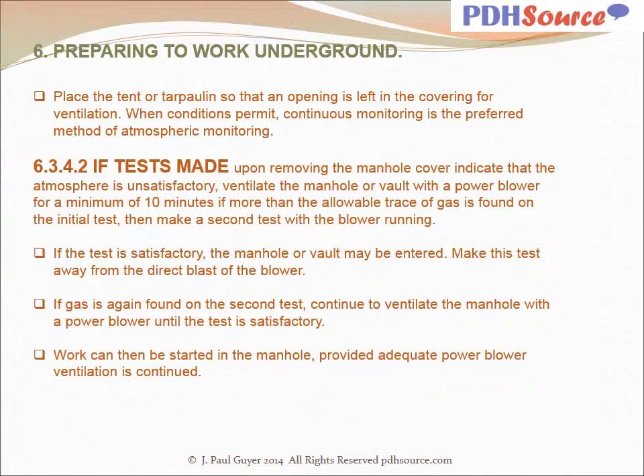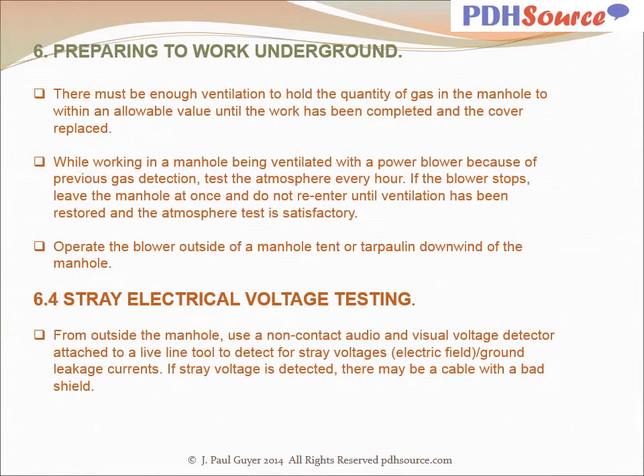Make this test away from the direct blast of the blower. If gas is again found on the second test, continue to ventilate the manhole with a power blower until the test is satisfactory. Work can then be started in the manhole provided adequate power blower ventilation is continued. There must be enough ventilation to hold the quantity of gas in the manhole to within an allowable value until the work has been completed and the cover replaced.